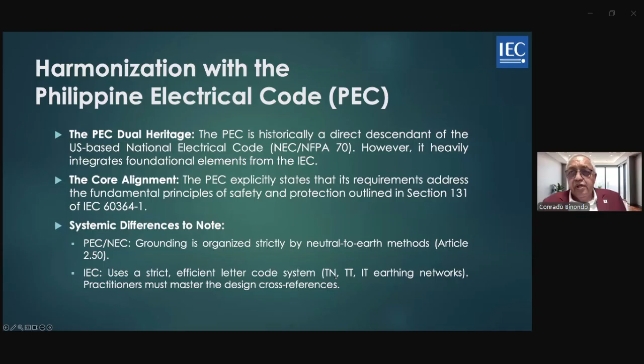So, grounded system yon. But when it comes to ungrounded, ito yung IT, yung isolated, yung neutral ng transformer or any part of the source, hindi siya naka-ground. Then, ganito yan. But there are usages. May mga application kasi ito. So, we can do that. We can use this one. And practitioners must master the design cross-references para magamit natin kasi minsan pag nag-specify tayo, we just use a general term, grounding system. But kung titignan mo yung installation, nandyan yung TN-S. Di ba? Very common. TN-S, nandun palagi siya sa ating mga installations.